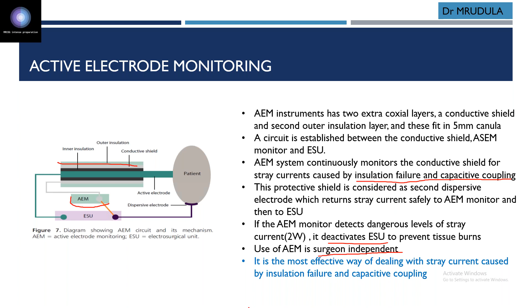So this AEM system continuously monitors the conductive shield. It monitors this instrument for insulation failure and capacitive coupling. These are the two things which are prevented by the use of active electrode monitoring. The protective shield is considered a second dispersive electrode, which returns stray current safely to the monitor and then to the ESU. If the active electrode monitor detects any dangerous level of stray current, it deactivates the ESU immediately. Use of AEM is surgeon independent, so it is not dependent upon the surgeon. It is the most effective way of dealing with stray current caused by insulation failure and capacitive coupling.